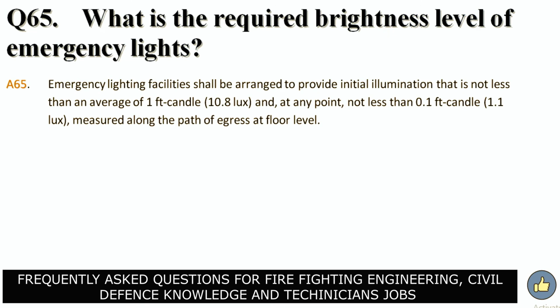Answer. Emergency lighting facilities shall be arranged to provide initial illumination that is not less than an average of 1 foot-candle (10.8 lux) and at any point not less than 0.1 foot-candle (1.1 lux) measured along the path of egress at floor level.